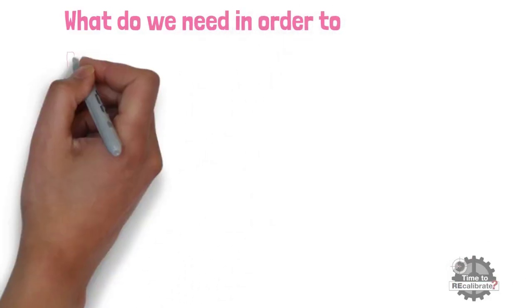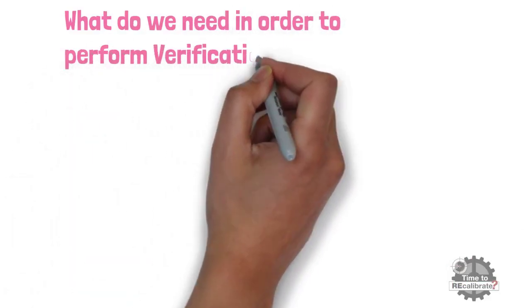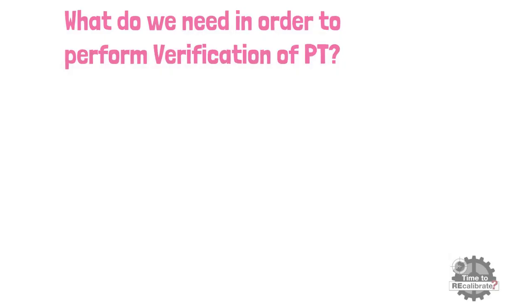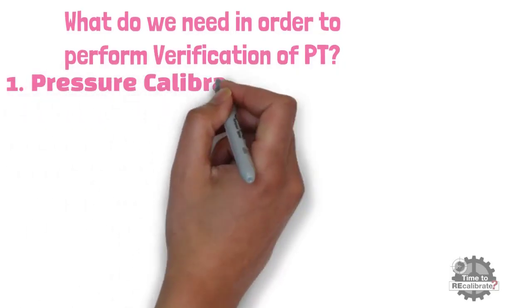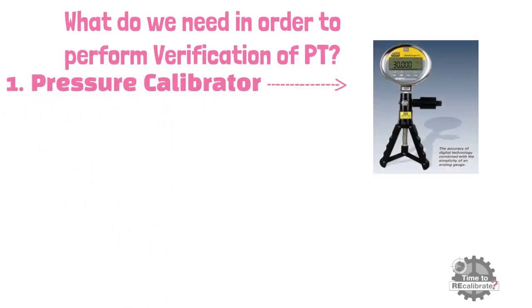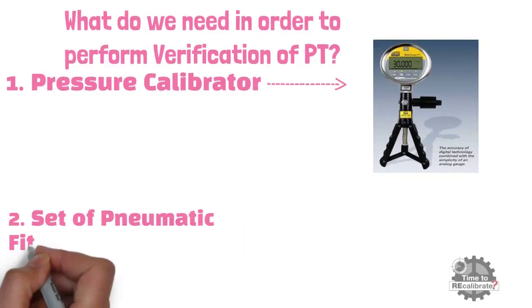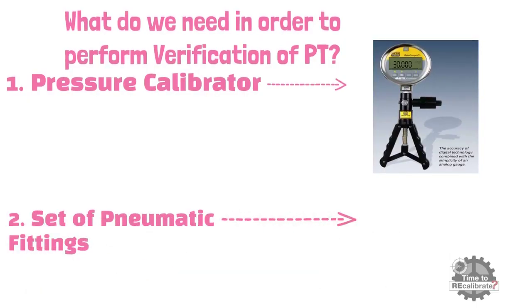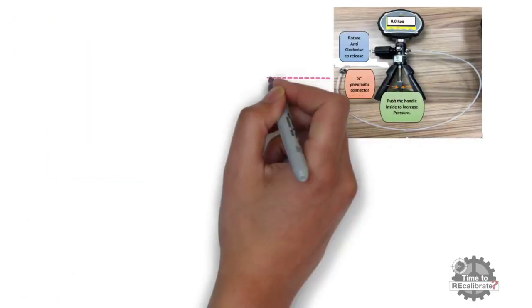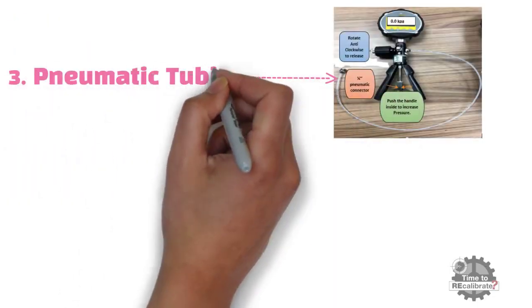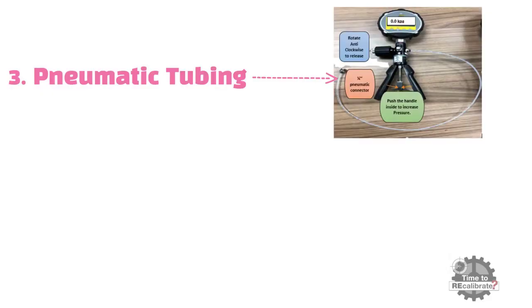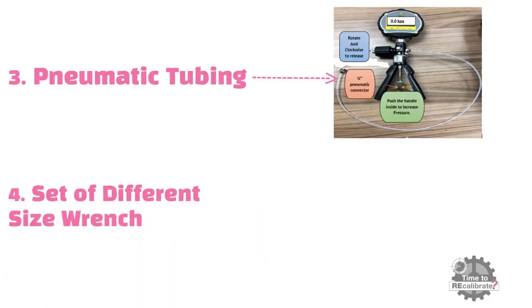What do we need in order to perform verification of pressure transmitter? First of all, we need a pressure calibrator. Secondly, we need a set of pneumatic fittings. Thirdly, we need pneumatic tubing. Last but not least, we also need a set of different size wrenches.